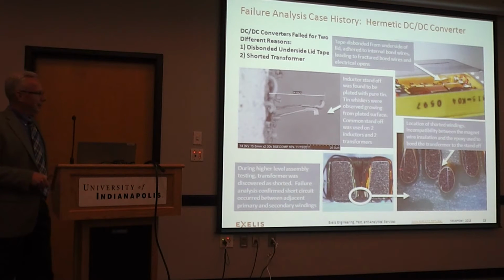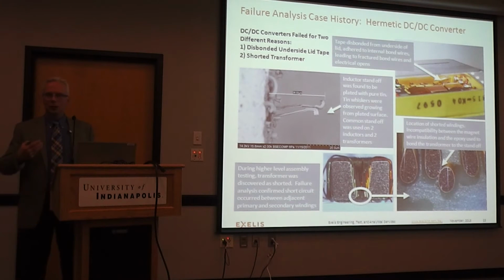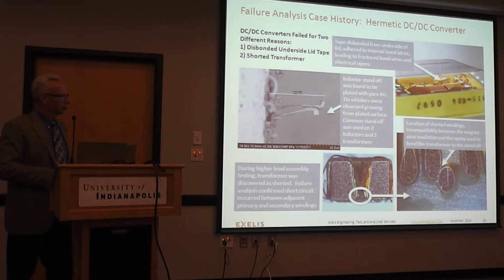But the shorted transformer is depicted in these last two images. This is a transformer that's been cross-sectioned, and this white circle shows the area of interest, magnified in the bottom right image. These two adjacent windings are electrically shorted. Now, magnet wire has a thin insulation that protects the wires from shorting against each other, but in this case these adjacent windings were shorted, and that was the cause of this module failure.